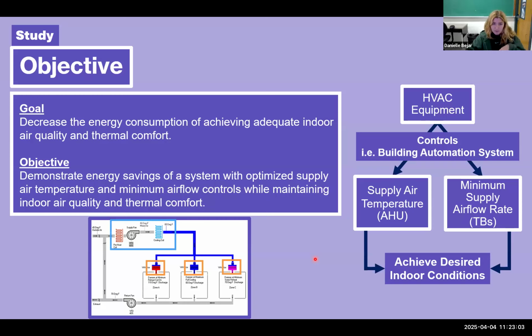So then more specifically, looking at the objective of this study, we wanted to demonstrate energy savings of a system with optimized supply air temperature and minimum airflow controls while maintaining indoor air quality and thermal comfort. And I wanted to include this figure to the right here so you can visualize. We have our HVAC equipment, the air conditioning equipment throughout the building, and it's all connected through controls. Maybe you've heard of a building automation system. So you can manipulate different parameters to achieve desired indoor conditions. And so what we're manipulating, like I said, is the supply air temperature at the air handling unit and the minimum flow rate at the terminal boxes. So there's no change to hardware. We're just changing controls.